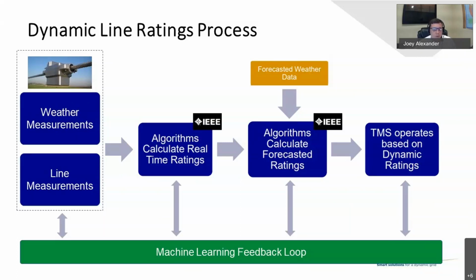It primarily takes two classes of measurements. The first we call line measurements, used to make sure we're staying within the limitations set by the utility. Typically lines are rated based on a maximum conductor temperature and/or maximum sag. These sensors on the line use line vibration to determine how much the line is sagging and what the line temperature is, ensuring we safely operate the line without too much sag or too much temperature. The temperature is also important because it feeds into the thermal model for line ratings.